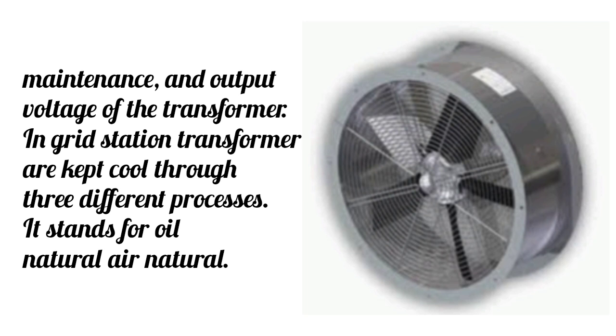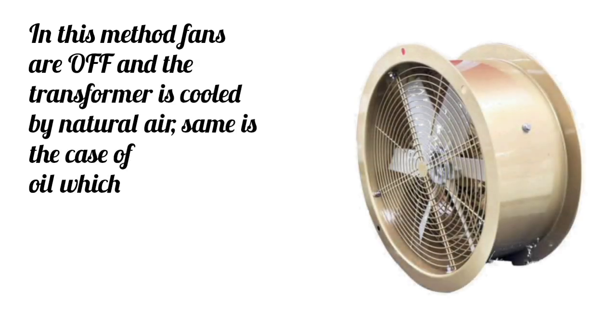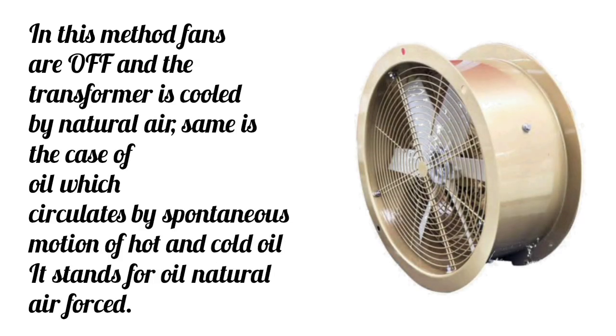ONAN stands for oil natural air natural. In this method, fans are off and the transformer is cooled by natural air. Same is the case of oil, which circulates by spontaneous motion of hot and cold oil.